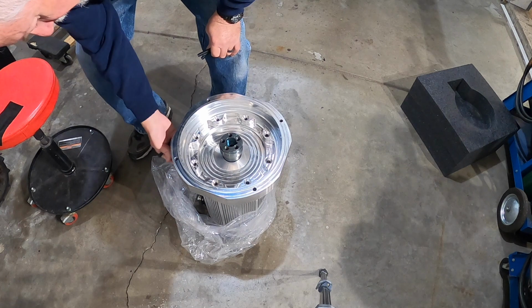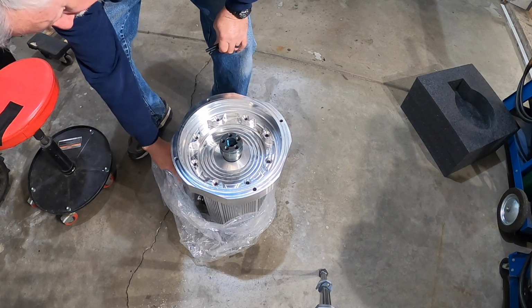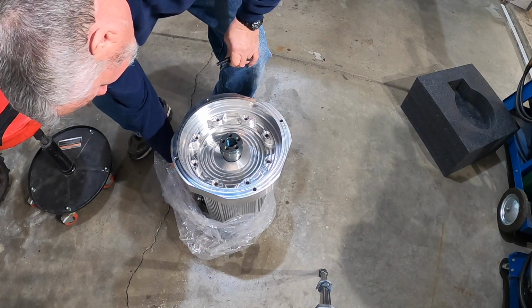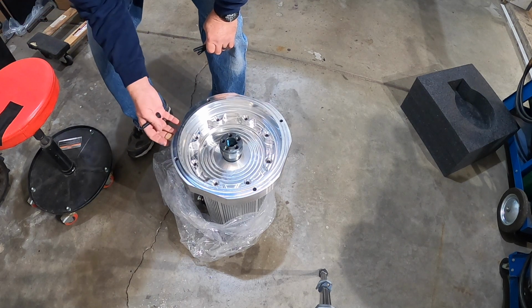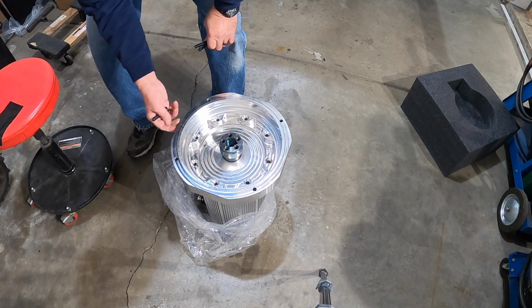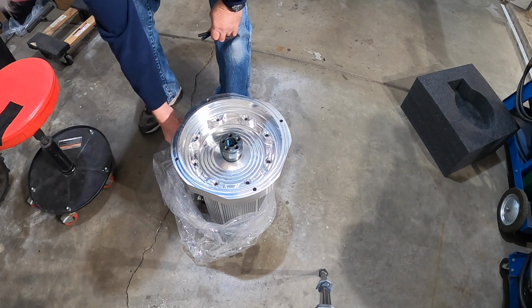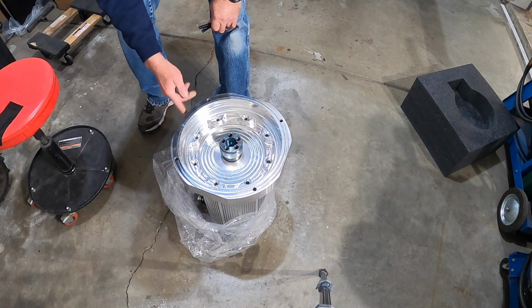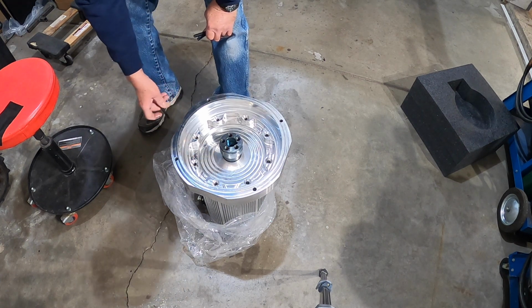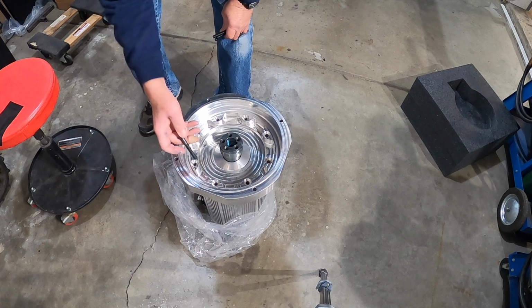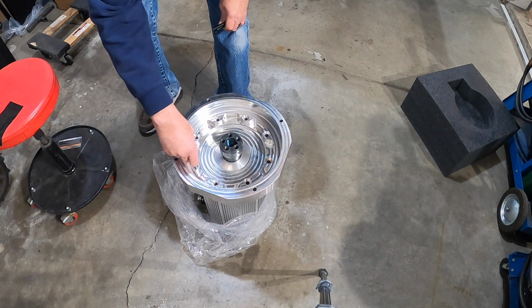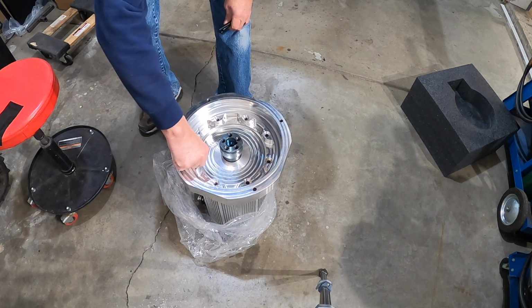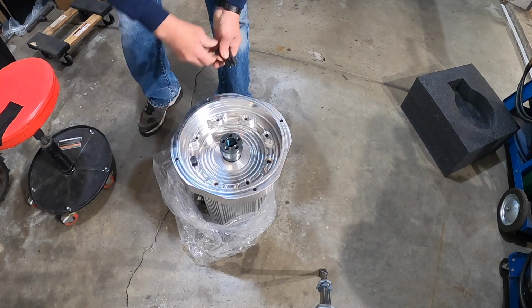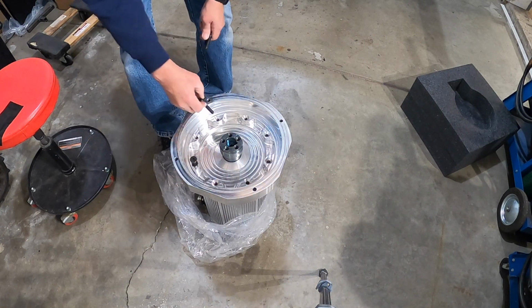Again, this is a B-face motor. On the side over here I have my 3-phase wiring connections, and this is the top where it has the bolt holes tapped where the motor controller is going to mount. So I have to make sure it's clocked in line with that. But I got everything lined up, got blue Loctite on the bolts, and get these installed.